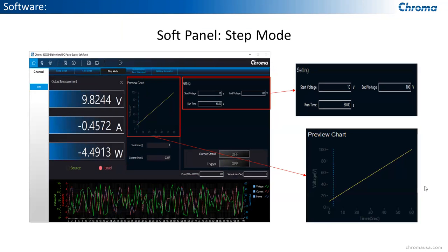Another way to do that is with what we call step mode. Here you can create ramps, as short as 5 milliseconds or out to multiple seconds, and you have a start and end voltage. You can inject it into the unit while the unit's operating at a fixed setting, or you can trigger it without having the output status on. It will trigger and run the ramp only.